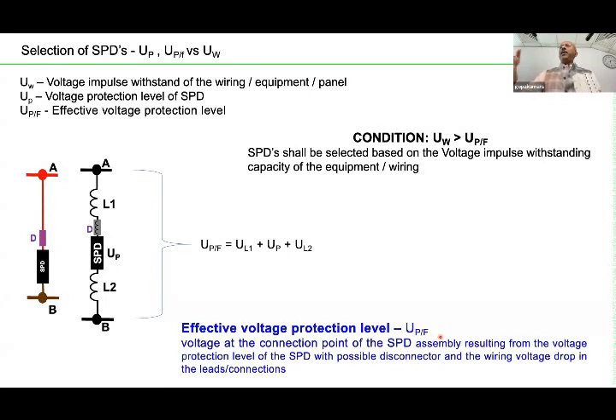That is the purpose. But because of the lines L1 and L2, more voltage drops on these wires. As a result, the effectiveness of the SPD is gone. So this is the condition we are supposed to always look at. I would say, when you install an SPD, the most important subject to be considered is the line length. The maximum allowed line length is 250 millimeters. That means with such a small wire, you are supposed to connect the SPD.